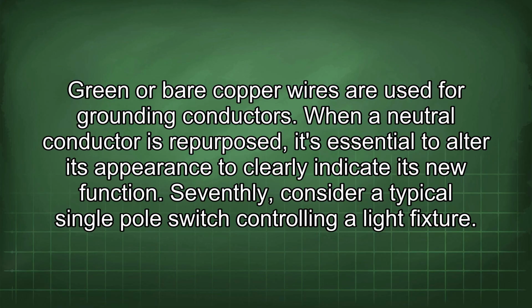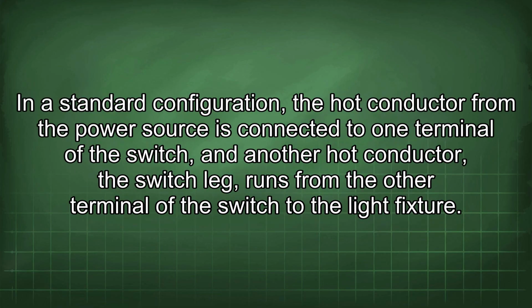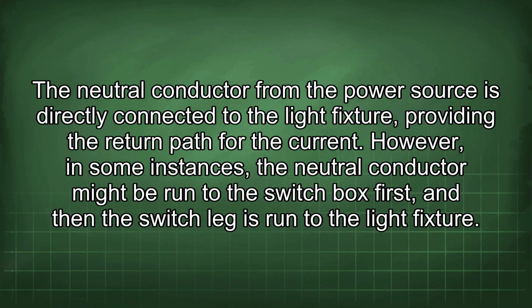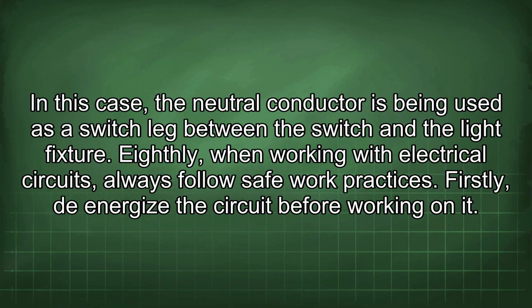Seventhly, consider a typical single-pole switch controlling a light fixture. In a standard configuration, the hot conductor from the power source is connected to one terminal of the switch, and another hot conductor, the switch leg, runs from the other terminal of the switch to the light fixture. The neutral conductor from the power source is directly connected to the light fixture, providing the return path for the current. However, in some instances, the neutral conductor might be run to the switch box first, and then the switch leg is run to the light fixture. In this case, the neutral conductor is being used as a switch leg between the switch and the light fixture. Eighthly, when working with electrical circuits, always follow safe work practices.